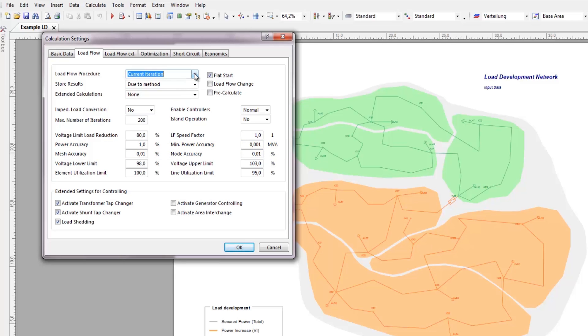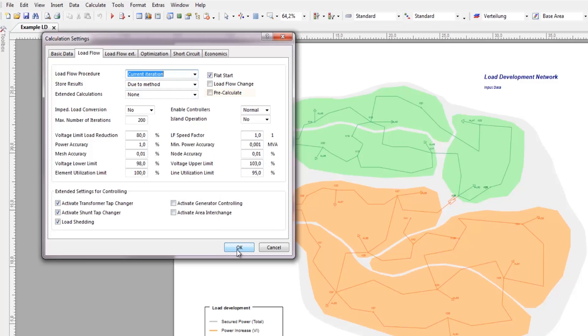The maximum number of iterations can be set in a pre-calculation to evaluate a solution even if the wrong input data is available. If network collapse is imminent, loads may need to be shed to maintain the possibility of emergency operation. Load and supply are assigned priorities, and if shedding becomes necessary, this is done according to assigned priorities.